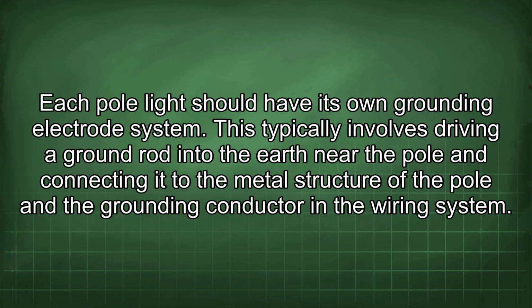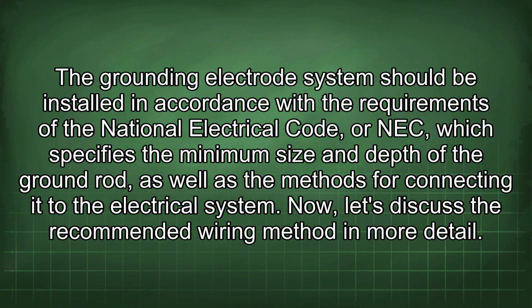Each pole light should have its own grounding electrode system. This typically involves driving a ground rod into the earth near the pole and connecting it to the metal structure of the pole and the grounding conductor in the wiring system. The grounding electrode system should be installed in accordance with the requirements of the National Electrical Code, or NEC, which specifies the minimum size and depth of the ground rod, as well as the methods for connecting it to the electrical system. Now let's discuss the recommended wiring method in more detail.